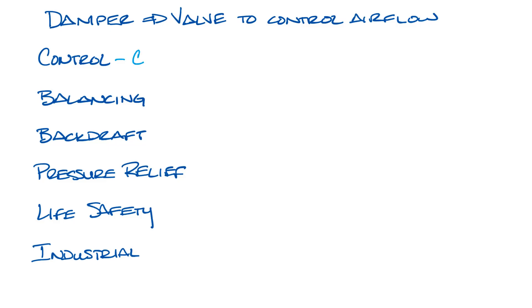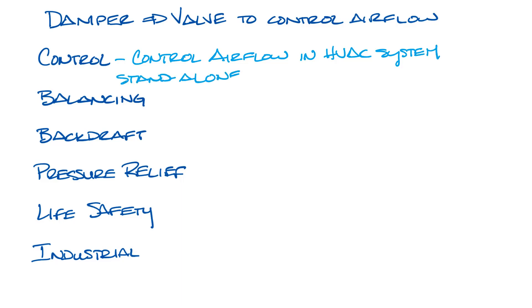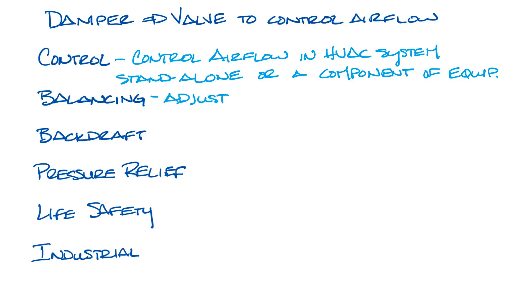Control dampers control the airflow in the HVAC system. These can be stand-alone in the system or be a component of another piece of equipment. Balancing dampers balance the airflow in the HVAC system. Balancing is essentially the process of adjusting the air to deliver the correct amount of airflow into a zone in the system.